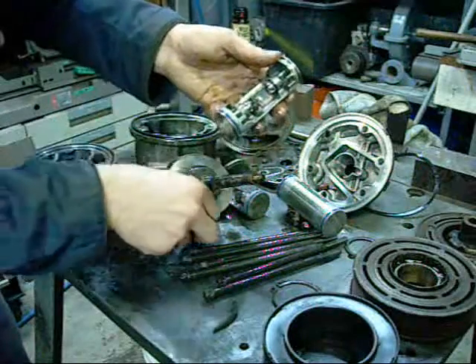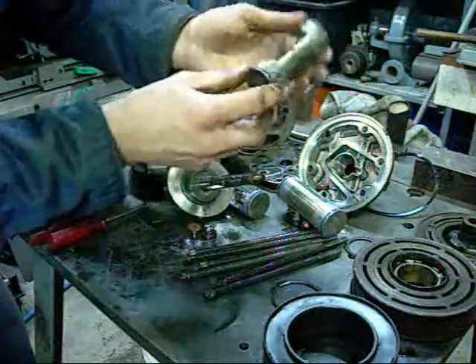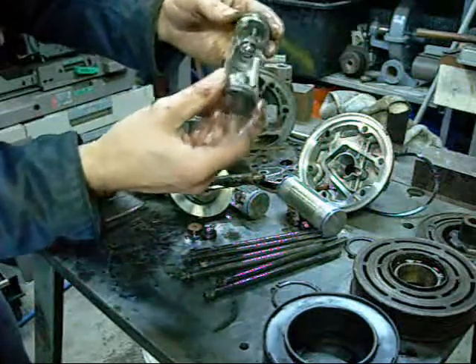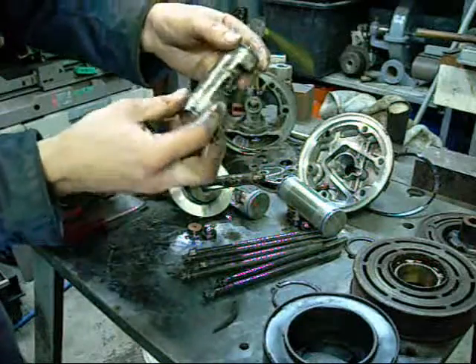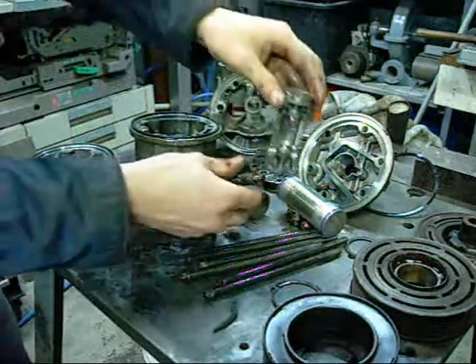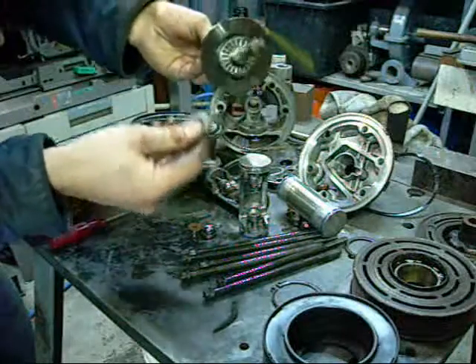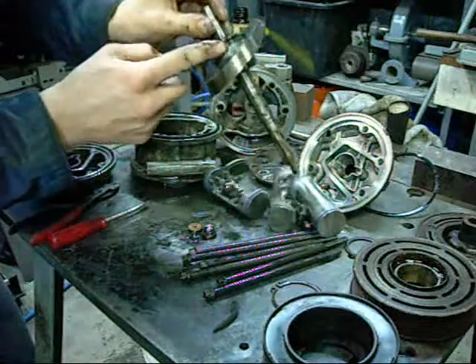There are little wear plates made of bronze or copper, and Teflon seals on either end. I suppose you'd call this a double-acting wobble plate compressor, with the thrust bearings on the end of the shaft.